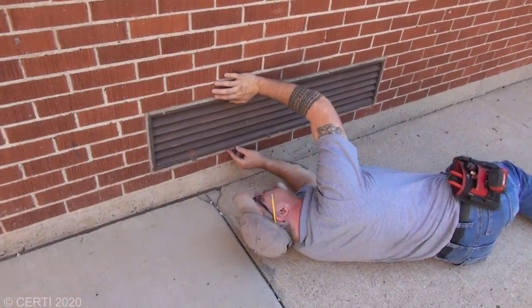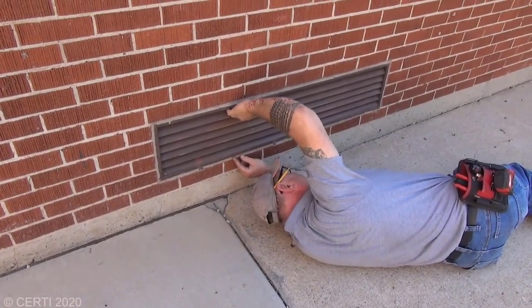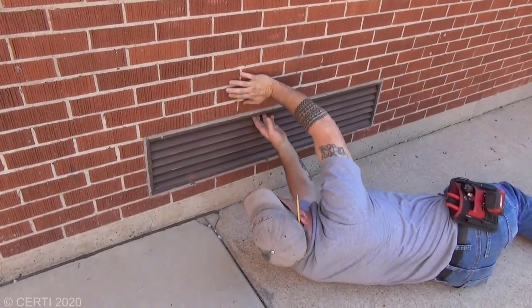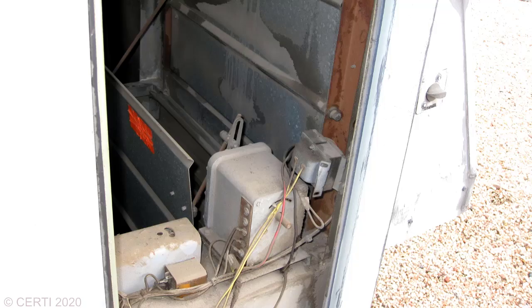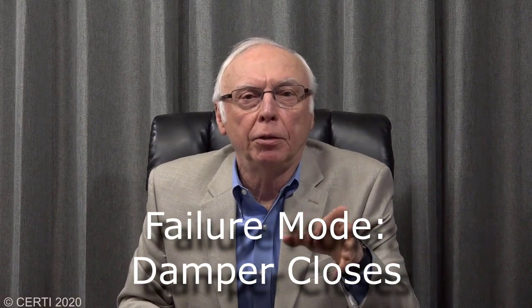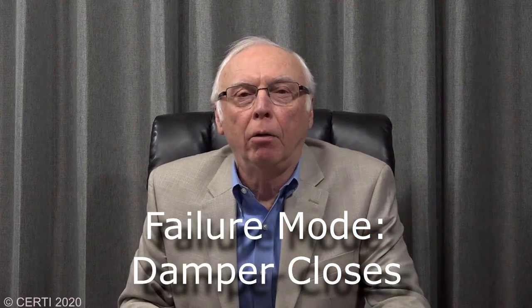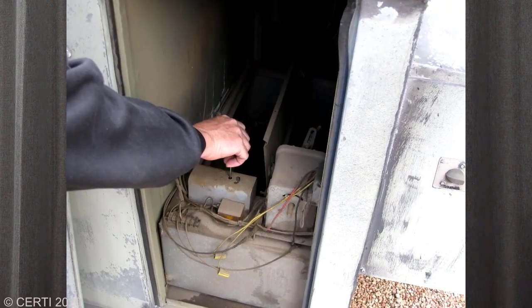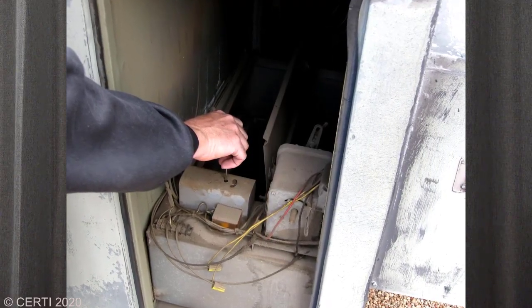Here is an example of an outdoor air intake on a unit ventilator where access to the filters from outside had been blocked when the brick was repointed. This condition prevented maintenance from changing filters, which over the years had become completely blocked and not allowing any outdoor air into the classrooms. These systems typically have temperature sensors and controls that will shut off extremely cold outdoor air. This is a safety feature to prevent freezing and damage to coils. Should these sensors fail, or the signal lines to them, whether electric or pneumatic, the damper will close in a fail-safe position, which would be the closed position, stopping all outdoor air. So maintenance of these controls and ensuring they have not failed closed is important for maintaining good air quality and low radon levels.